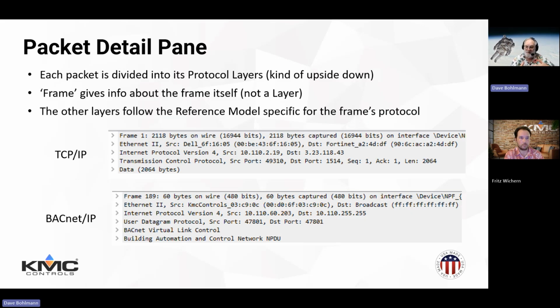It's what we call connectionless, which means you send out a message and there's nothing in the drivers on those machines for you to really know that it got the message or what it's going to do with it. So BACnet has to add its own handshaking, and that comes in these layers down here.